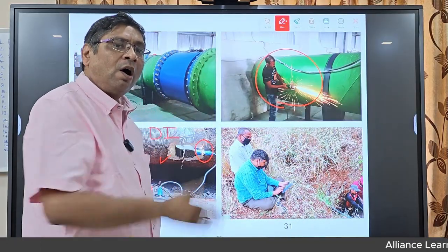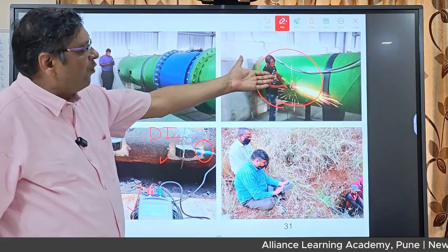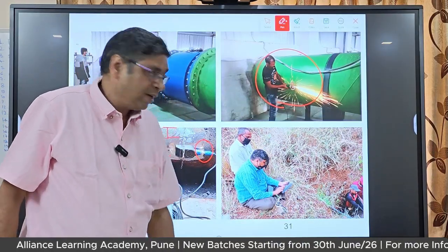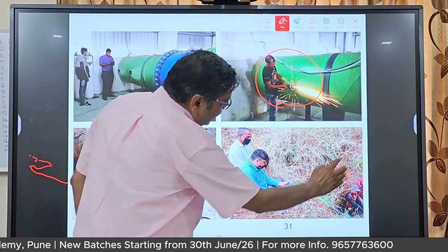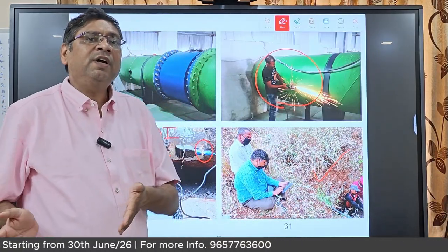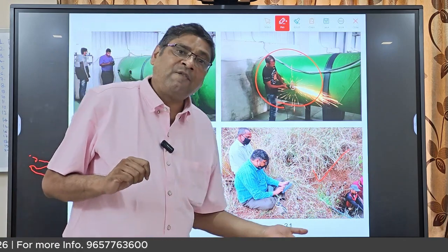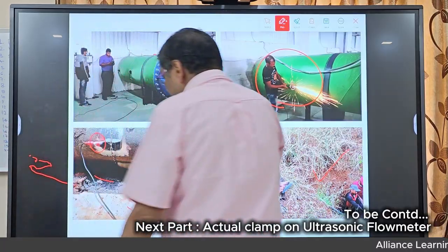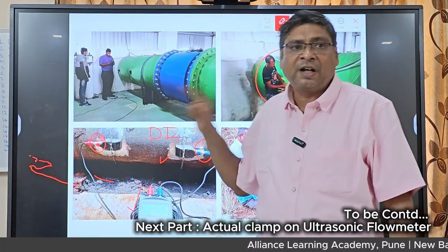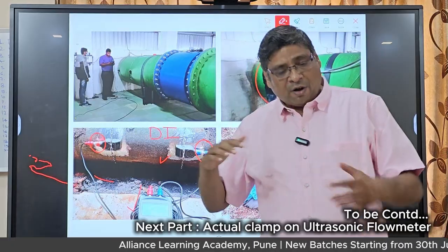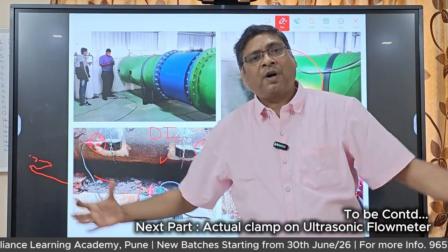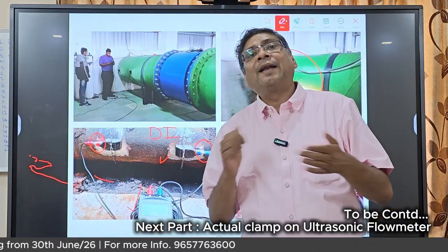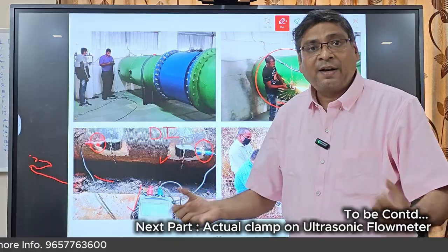This we all use for auditing purposes. Here in this plant, we are checking the efficiency of the pump and motor machineries. In this case, we are just measuring the flow, how much it is giving, or if a new plant was installed, we have to know whether they are giving the guaranteed flow or not. In this application, these are Indian Railways applications where we did the water audit. All the water going to the railways, we did the audit to calculate the NRW of that railway division.